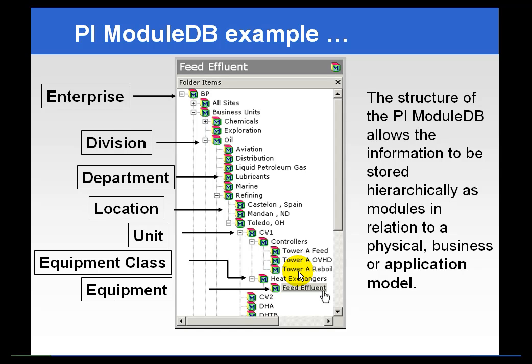This brings us back around to ACE, in that ACE uses the same sort of hierarchy and the same sort of information in its calculations. You can develop one calculation — not using a tag name per se for the input — but by using an alias or a context, you can apply that same calculation across many different modules through a few simple point-and-clicks with the mouse, as opposed to developing individual calculations, compiling them, registering them, and scheduling them. So PI ACE can use the PI Module Database to automate or propagate its calculations across many different areas and layers of the organization.